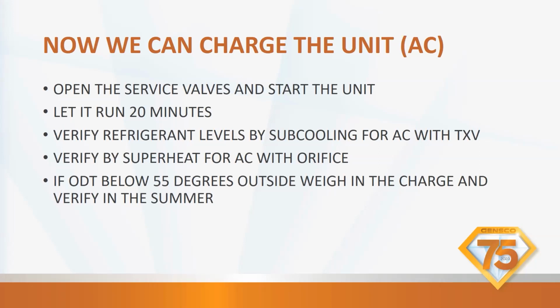Okay. If the outdoor temperature is below 55 degrees, you can weigh in the charge and then you can go back and verify it in the summer. Okay. Because you're probably not going to be starting up the AC when it's real winter outside. You know, it's not good for it. So you probably don't want to do it.